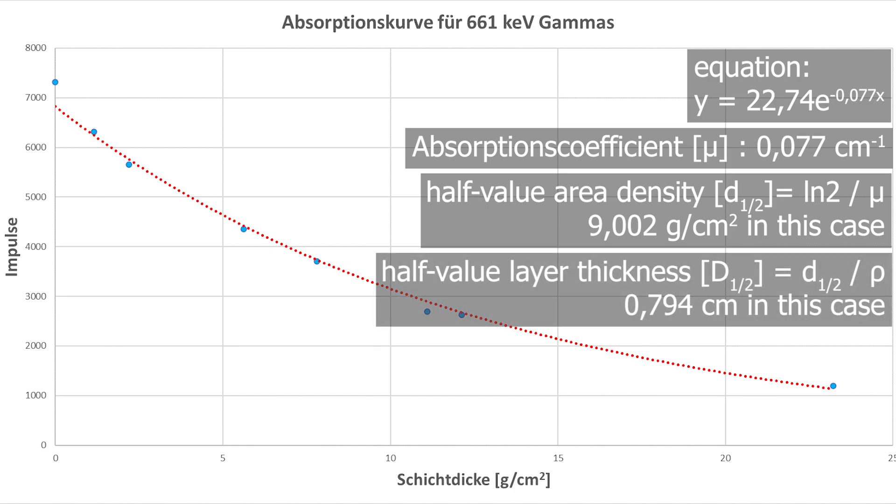In our case it's 9.002 grams per square centimeter. Our calculation isn't over yet. We want the half value thickness; to get that, divide by the density of the material. In our case it's lead which is 11.342 grams per cubic centimeter. In the end you get a half value thickness of 0.794 centimeters.